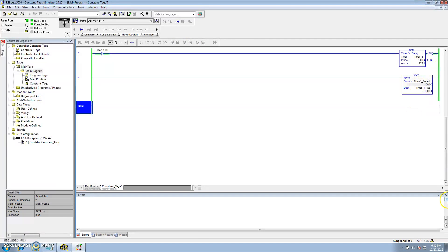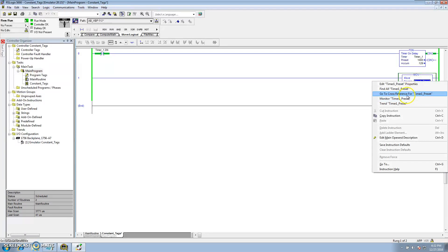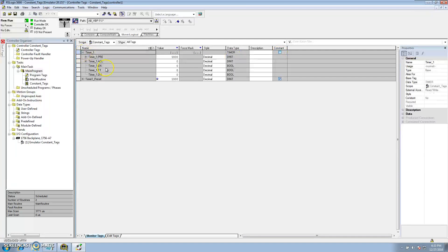That's the downfall to using it, but realistically it's not a downfall — you want this to be constant, you don't want it changed, so you force someone to go to the monitor tag section and change it there. Also note that you cannot make a timer a constant tag; there are some instructions you can't do that with. It's mainly for tags like integers, reals, floats, and similar data types.